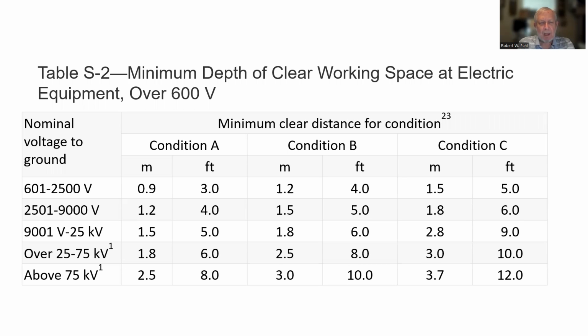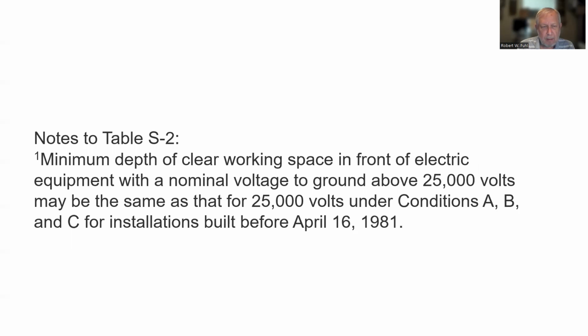Minimum depth of clear working space at electric equipment over 600 volts. So there's your nominal voltage to ground, 600 to 2500, 3 feet. Condition B, 4 feet. Condition C, 5 feet. And there's your second one, 2501 to 9000, 4 feet, 5 feet, 6 feet. And this is a minimum depth of clear working space.